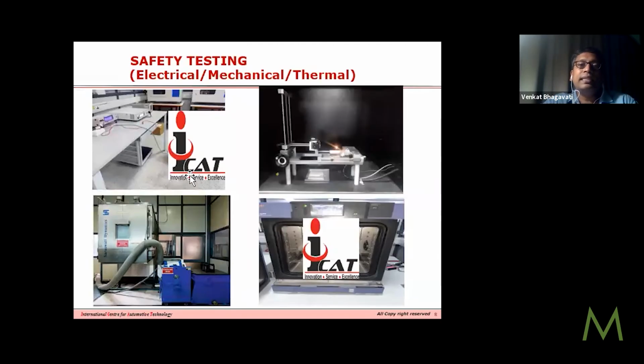Sure. So here, on the left, you can see the leakage current measurement setup. I have covered the device with our lab logo because we can't show the device. Leakage current and dielectric strength tests are very crucial tests which most devices undergo. Then on the right side, you can see the flame test, because flammability testing is quite important, and it's done for any product safety category.